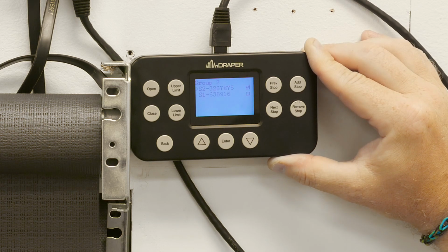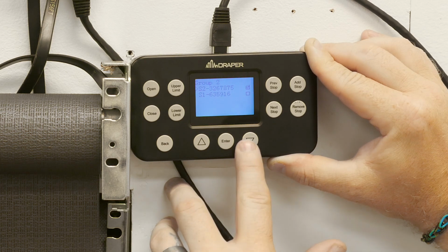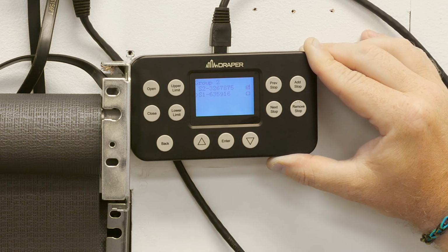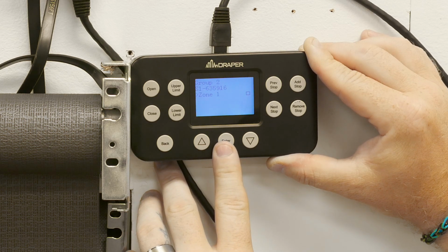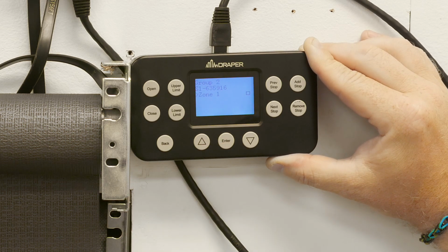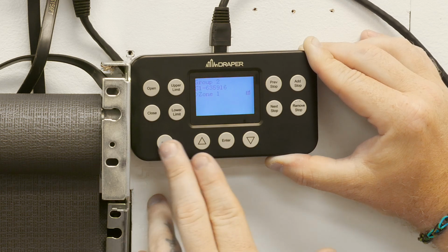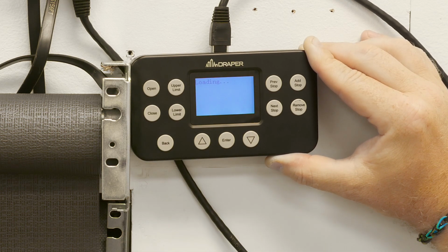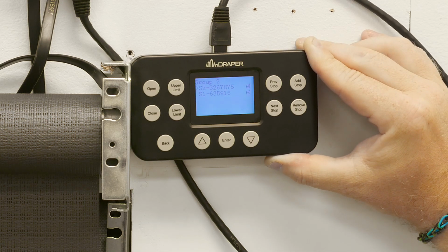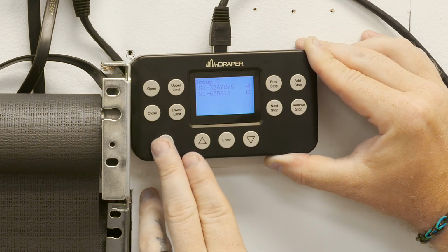All right, perfect. My 2-zone switch is now programmed to group 2, so now I'm going to go in and set up my S1, my single zone switch. So I'm going to select that by hitting enter. And I also want it to be part of group 2 because I want my single zone switch and zone 2 of my dual zone switch to operate the same shade group. So I'm going to select enter. This zone is now part of group 2, hit back. And now both my single zone switch and zone 2 of my dual zone switch are going to operate the same group of shades. Very easy to do all of this programming directly from the limit tool in one accessible point.